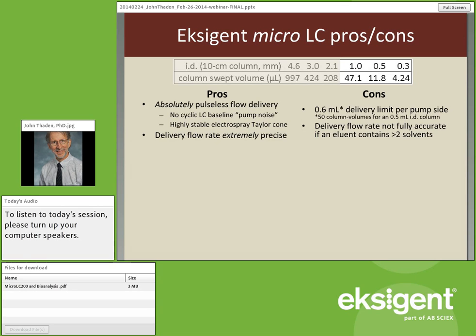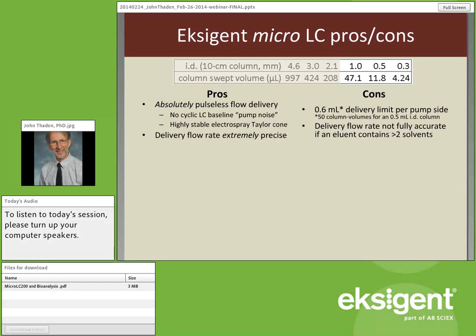The pros of micro-LC systems are significant. First, there is no pump pulsation — these pumps do not reciprocate like conventional HPLC pumps. They're like a large syringe pump: no push-pull-reload cycles. This means no pump noise, and the electrospray Taylor cone is extraordinarily stable — almost a deciding factor for MS work. The delivery flow rate is extremely precise, in part because of the pump design and also the very small void volume of these systems. Our system void volume (excluding the 11.8 µL column swept volume) is approximately 2.4 µL.